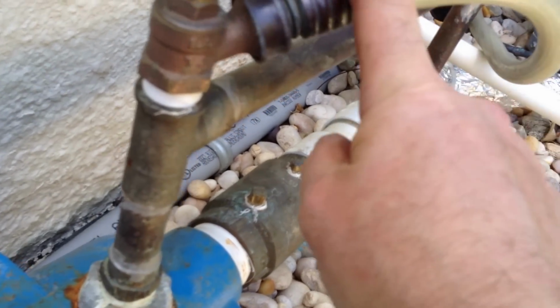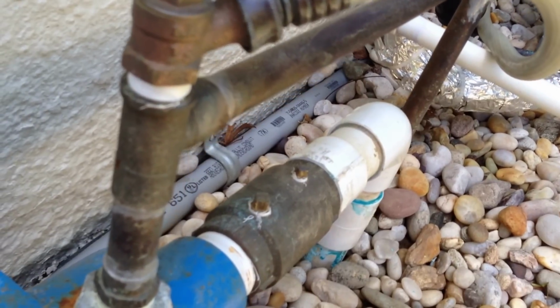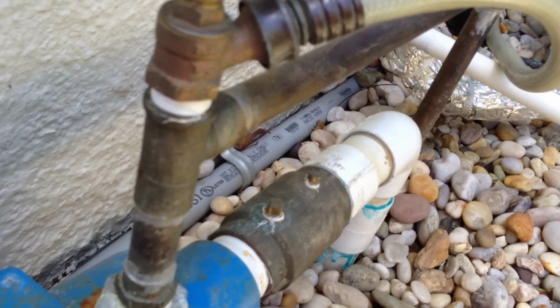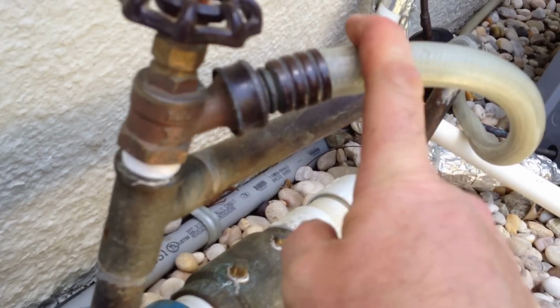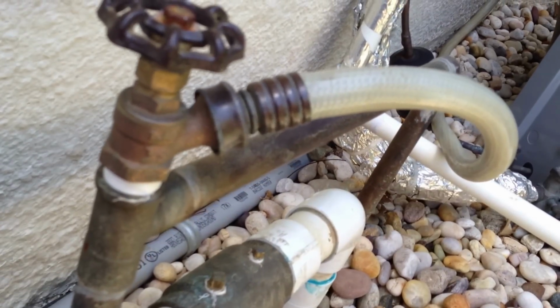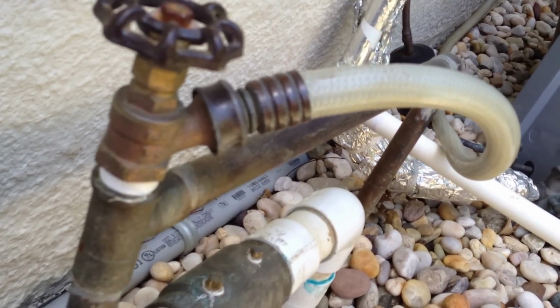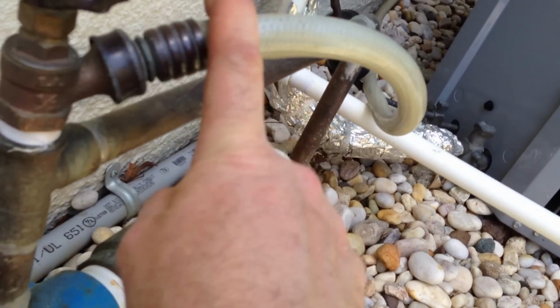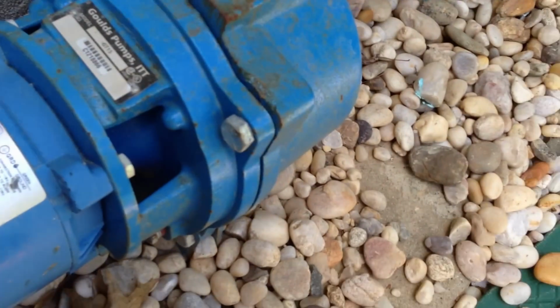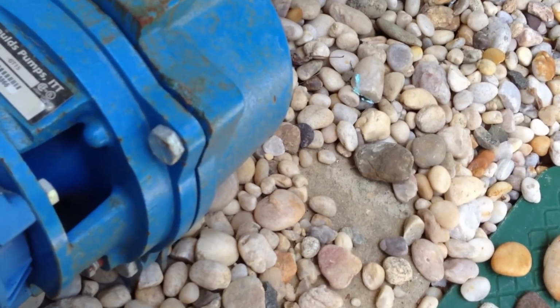Because if they make this electrically one zone, and you have it hooked up to its own zone, then if someone ever turns it on to that zone, and the hose isn't open, the pump is going to be pumping water with nowhere to go, and that's going to burn out your pump in an hour. That'll destroy your pump.